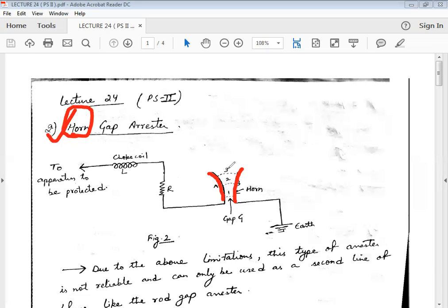When the surge goes out or is demolished, the arc is also demolished, because there is no current intensity left behind to maintain the arc. Inductance also opposes the change in current during the normal supply frequency, and resistance also controls it. So there will be no current after the surge disappears, but current appears in the case of metal rod arresters.